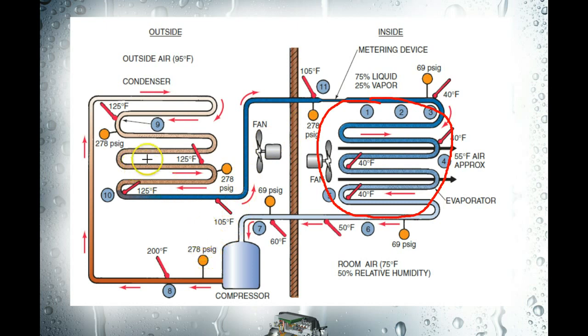On the other half of the cycle, you see that the saturation temperature is 125 degrees Fahrenheit in the condensing coil. The outdoor air temperature is 95 degrees, so while that is hot to us, it's cool in comparison to the 125 degree coil.